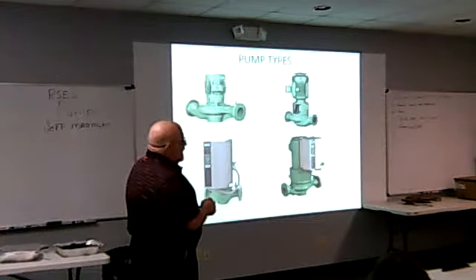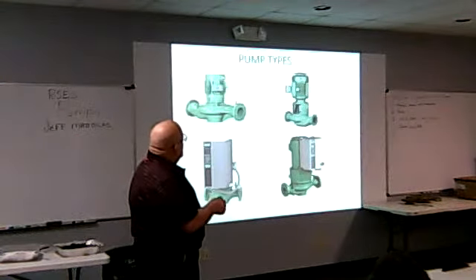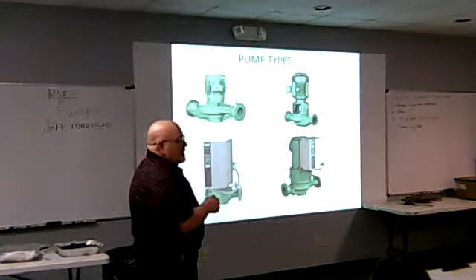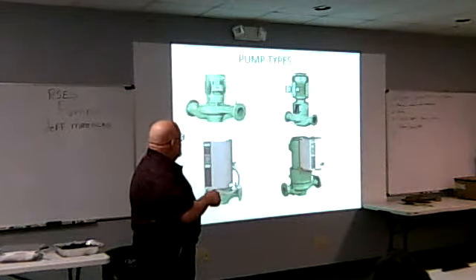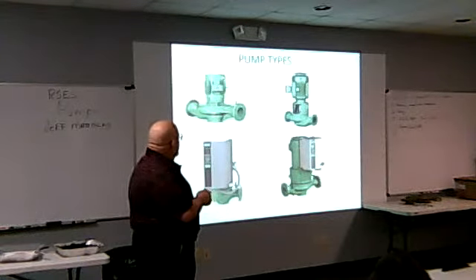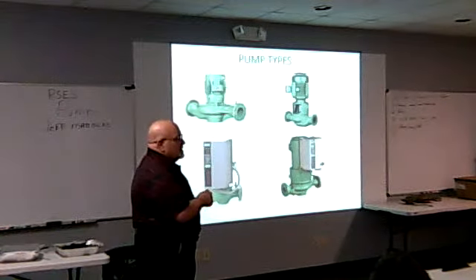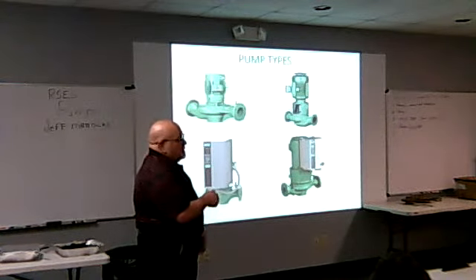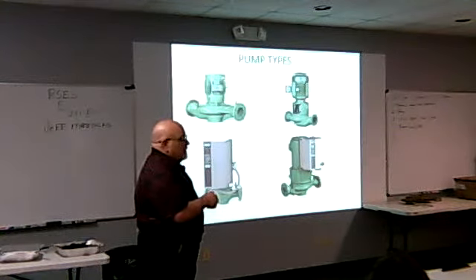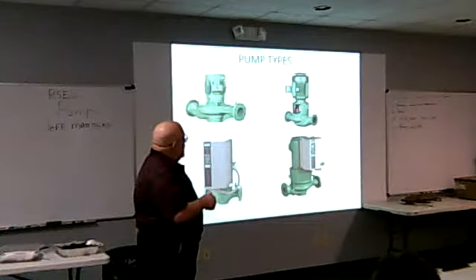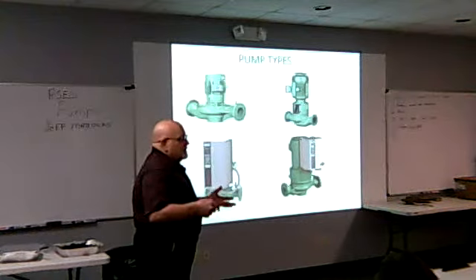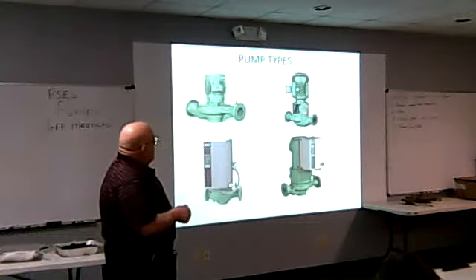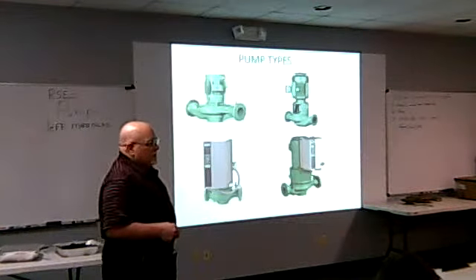This one is direct driven, just like the 1900 series were. This is split coupled. Same pump, same impeller, different motor. And again, this one I have to break the wet side to fix it. These go all the way up to about 150 horse now, 14 by 14. And if you need to replace the motor, you can lift the motor off and not have to break the water side. And we make these with an internal and an external seal.